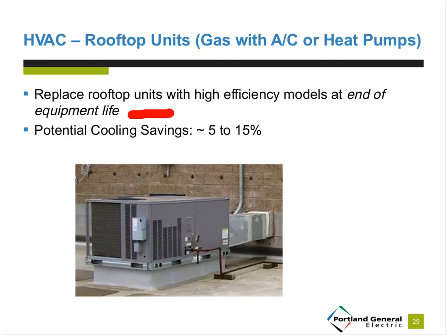The general rule of thumb is 20 years. That's when the HVAC system starts losing efficiency just because of the developing technology. But it really is just a motor, and in theory it's going to run 50 years as long as you keep it maintained. I would say that you need to have an annual maintenance plan for your HVAC system. You know, that means cleaning the coils, making sure the filters are clean and that it's running correctly.